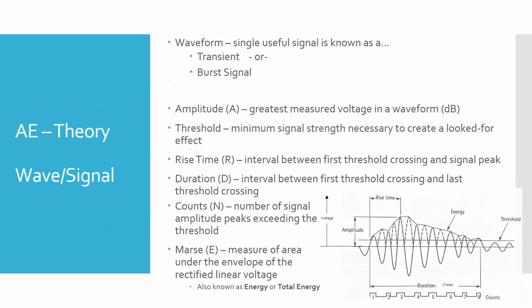Counts is the number of sine waves, the signal amplitude peaks, that cross our threshold. They've shown a couple of things here. You've got your primary wave, and then you've got an absolute value wave. You can see where they take all the peaks that are below, in the opposite direction, and they've drawn them in dashed lines going above. But we look at the positive peaks that cross the threshold. So in this case, there are 8 peaks: 1, 2, 3, 4, 5, 6, 7, and 8 that cross the threshold. So that's called the count, our signal count.